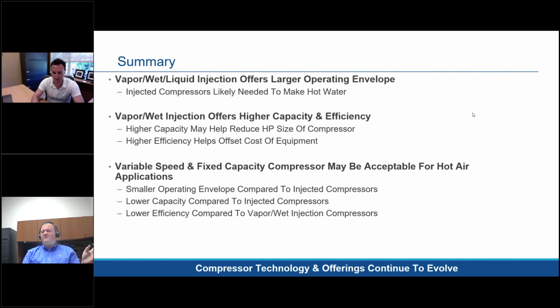Typically if you're trying to make 55-degree supply air, some OEMs may require an evap temperature or saturated suction temperature of 48 degrees. Well, one option that they have, they can change what their evap coil is doing, or sometimes that new refrigerant may have better heat transfer properties. Where instead of operating at 48 degrees evaporating temperature in order to make 55 degree supply air, they may be able to bump that up to 49 or 50 degree evap temperature to make that same cooled air. And that has a drastic increase in what the efficiency of the compressor in the system would be, because you're lowering the compression ratio of the compressor. So it's doing less work and it's getting more efficient, and you're getting the same supply air temperature as well. But that question is really going to need to come from the specific OEMs on their systems and how they're applying these compressors.